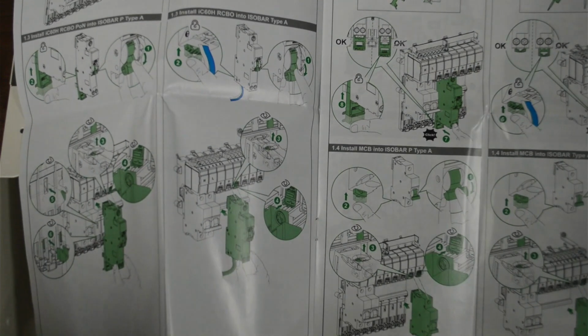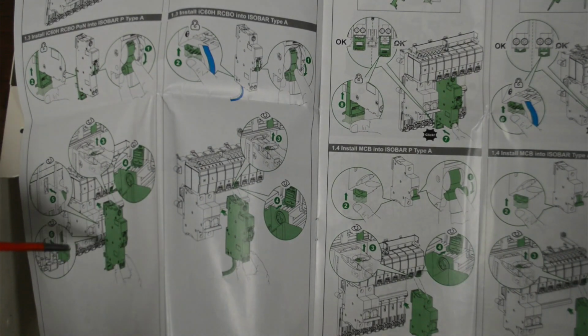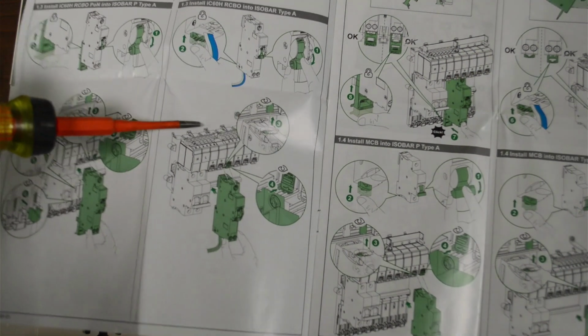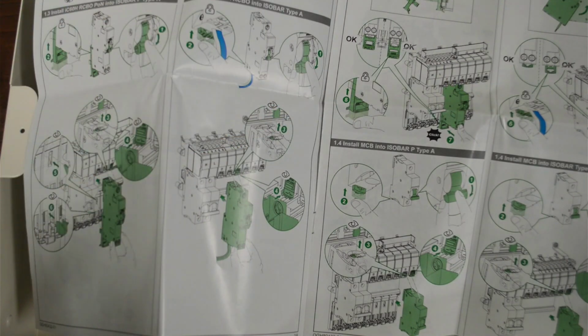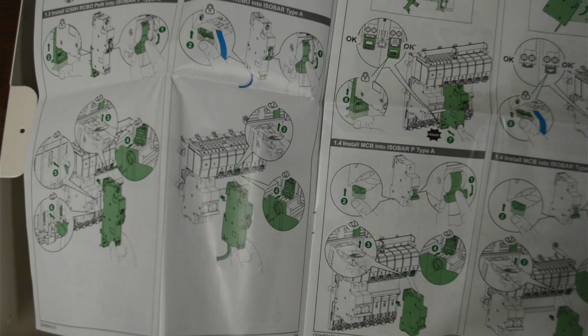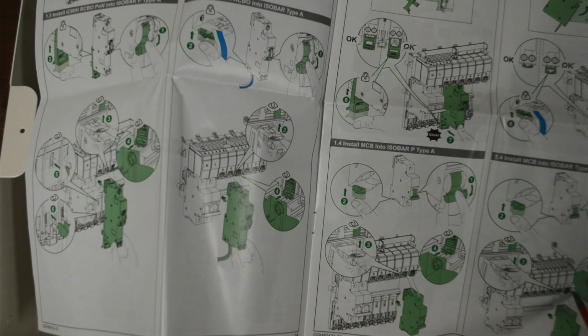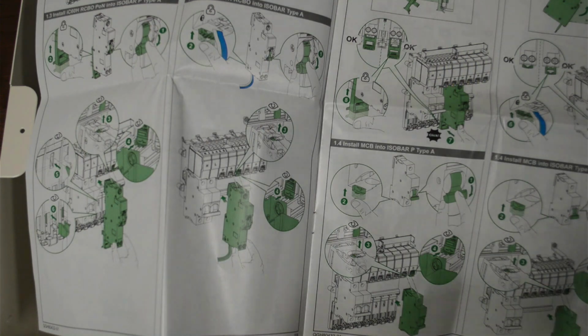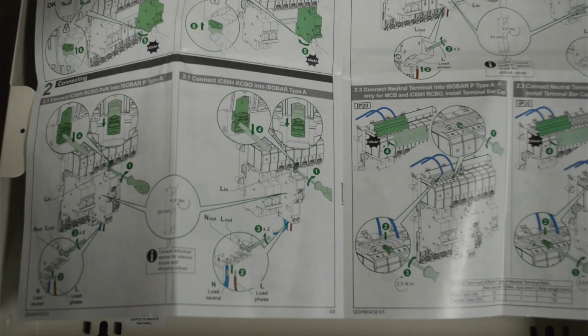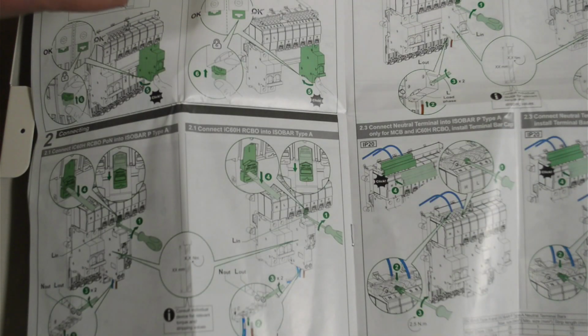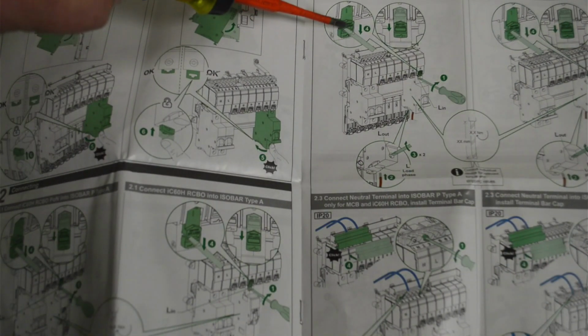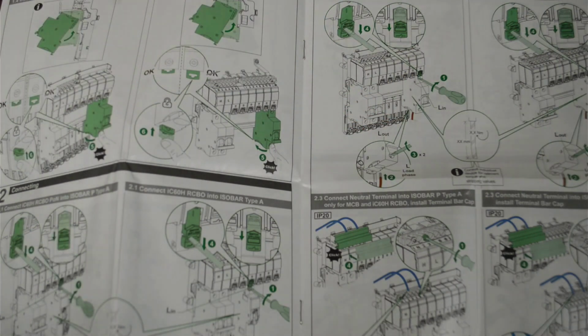It also gives you a bit of information about how you would remove and install these breakers. So as I showed you with the little yellow tag, you can see that over here. Same there, locking it in, and it explains to you about the cover over the MCB or RCBO screw terminal, so you can see that there. Again, if you swing out to the next page, I think it gives you some more pictures of that. So drop that down a little bit, you can see that there, just at the top where it's explaining about the lock for energizing that particular way on the board.